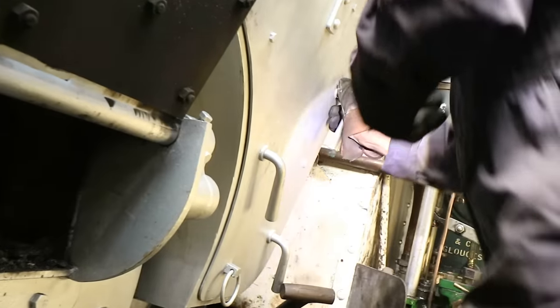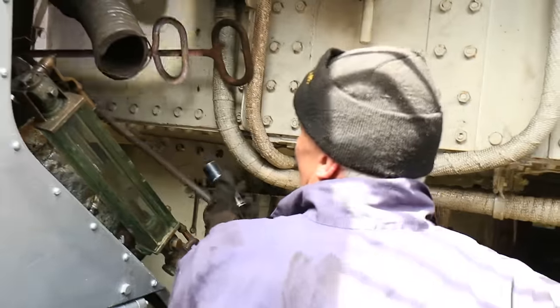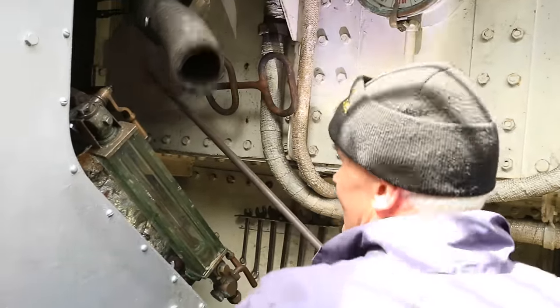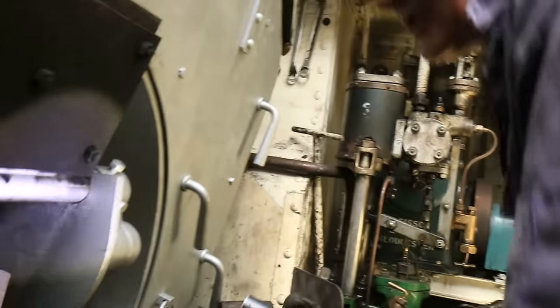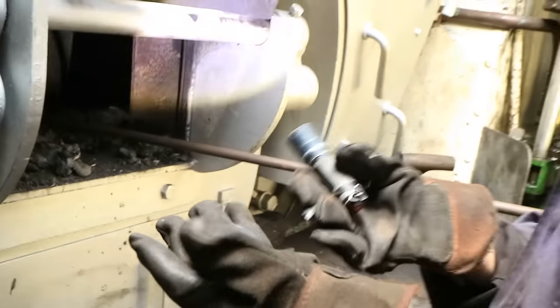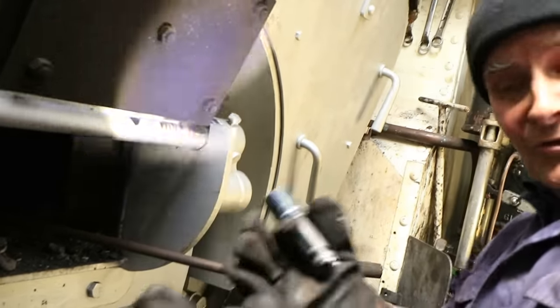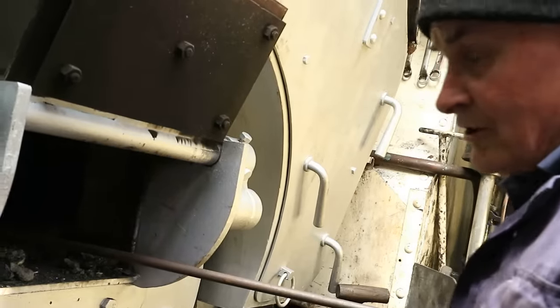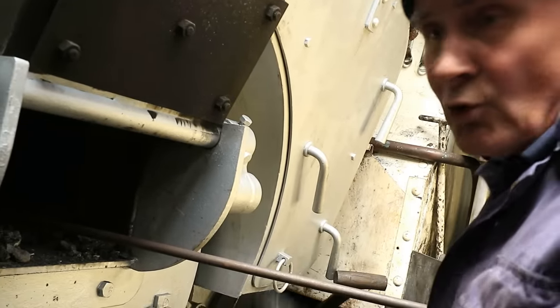This is nearly smokeless, very high heat value. You get a more efficient boiler out of it. And you can't really see it here, but when you burn Welsh dry steam coal, it swells up. So if you take a lump of coal this sort of size, 2 inches across, if it's half burnt, it'll be 4 inches across or more, opening out like a cauliflower. You can see its fossil origins. But as it swells, it improves the surface, enlarges the surface area. It gets hotter and hotter.